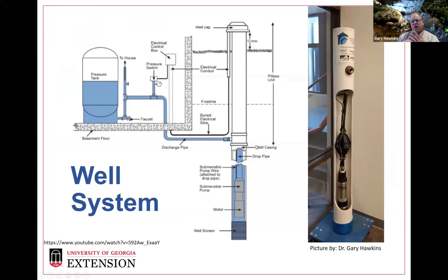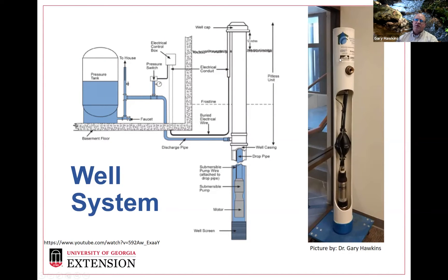For a home well system, you would have the casing drilled down into the aquifer with a submersible pump. Water is then pumped into a pressurized tank, and that pressurized tank pushes water to the house. A pressure switch controls when the pump turns on and off based on pressure in the tank. The picture on the right is a cutout from Virginia Tech showing the white PVC casing pipe, the pump, and a stabilizer — a bubble that keeps the water line centered within the well casing.